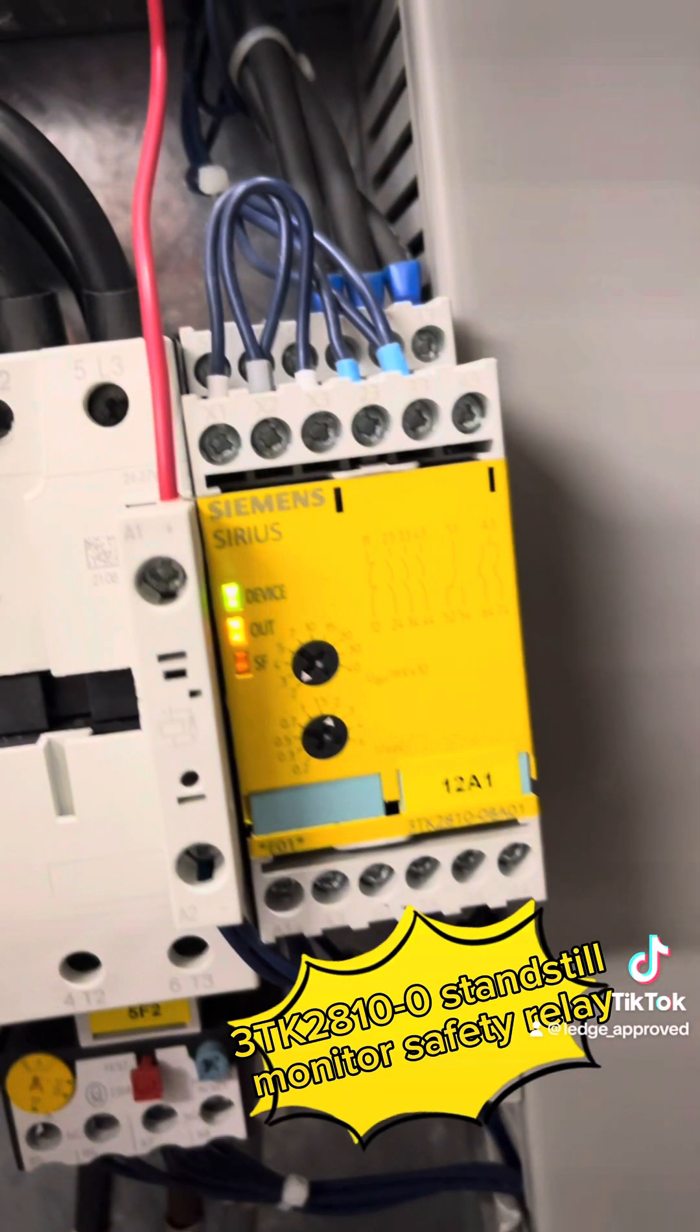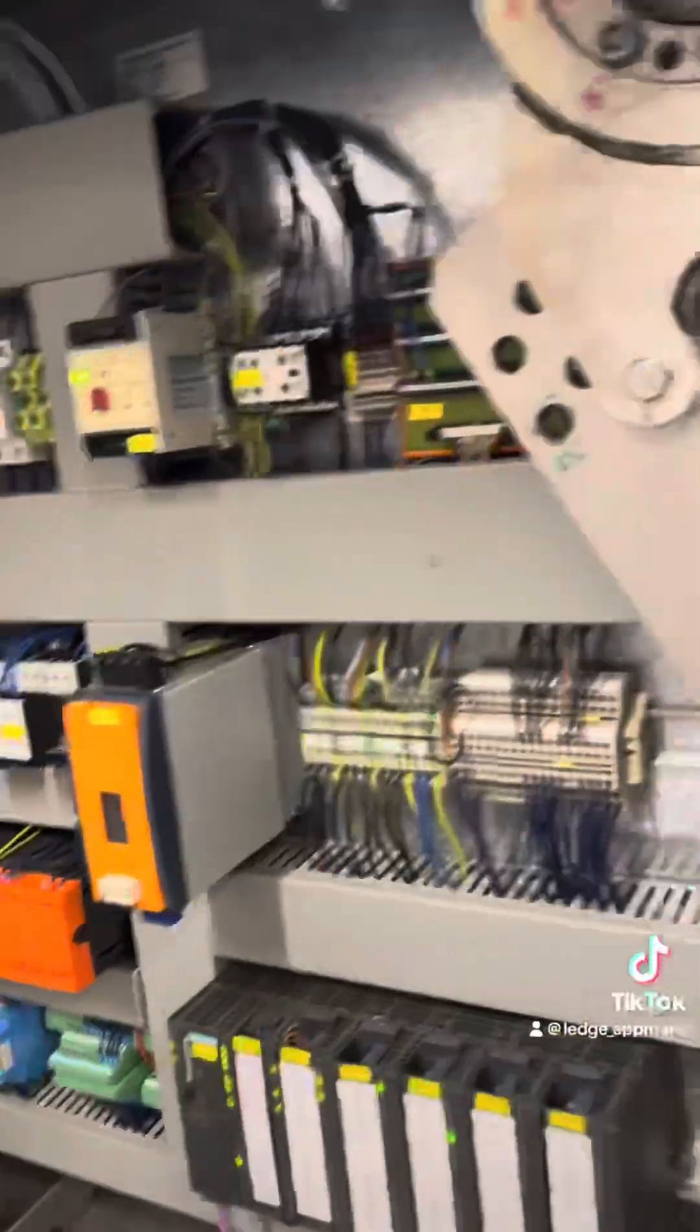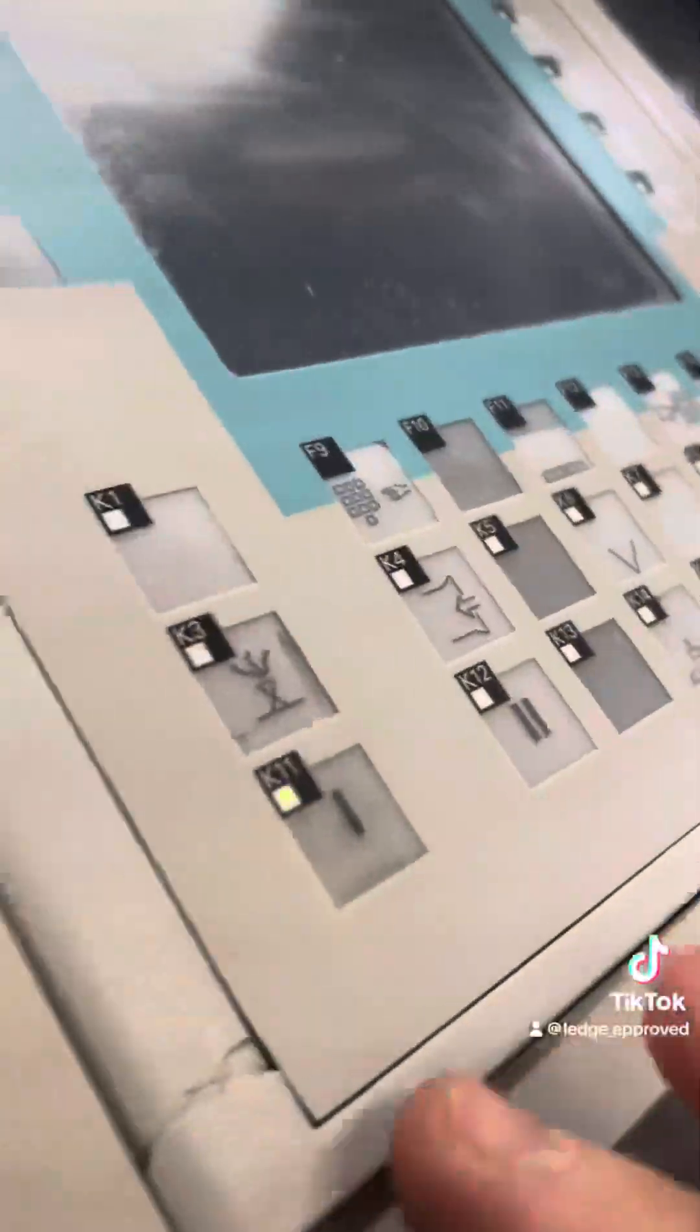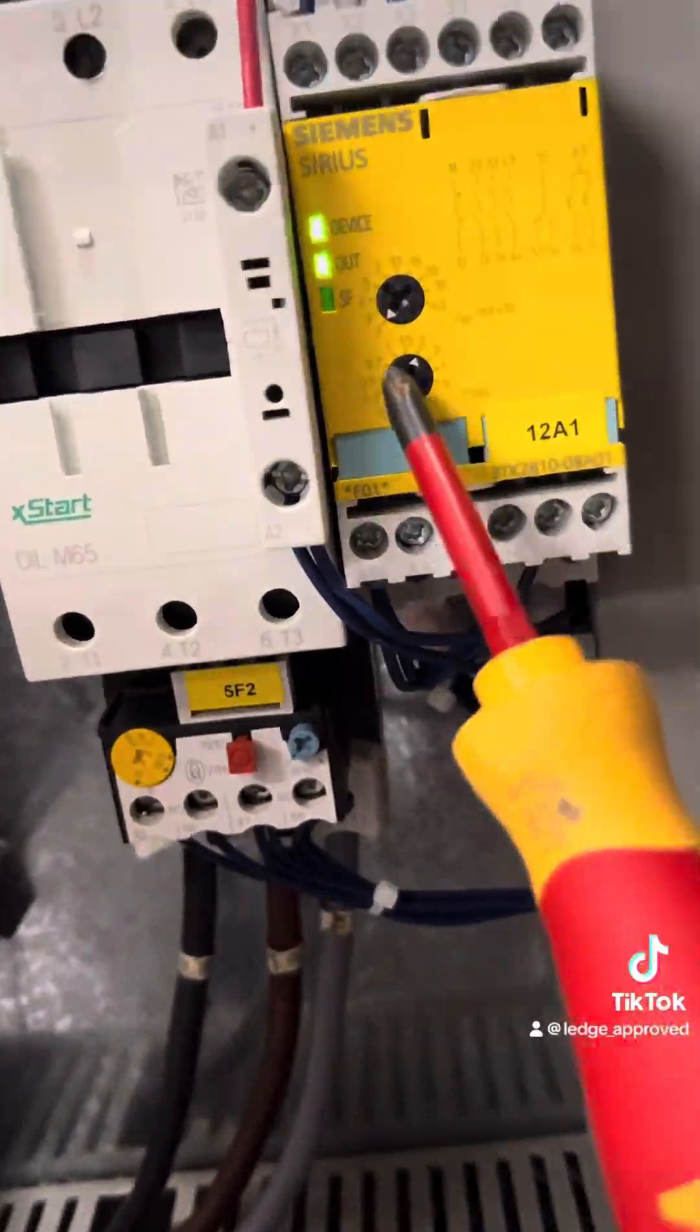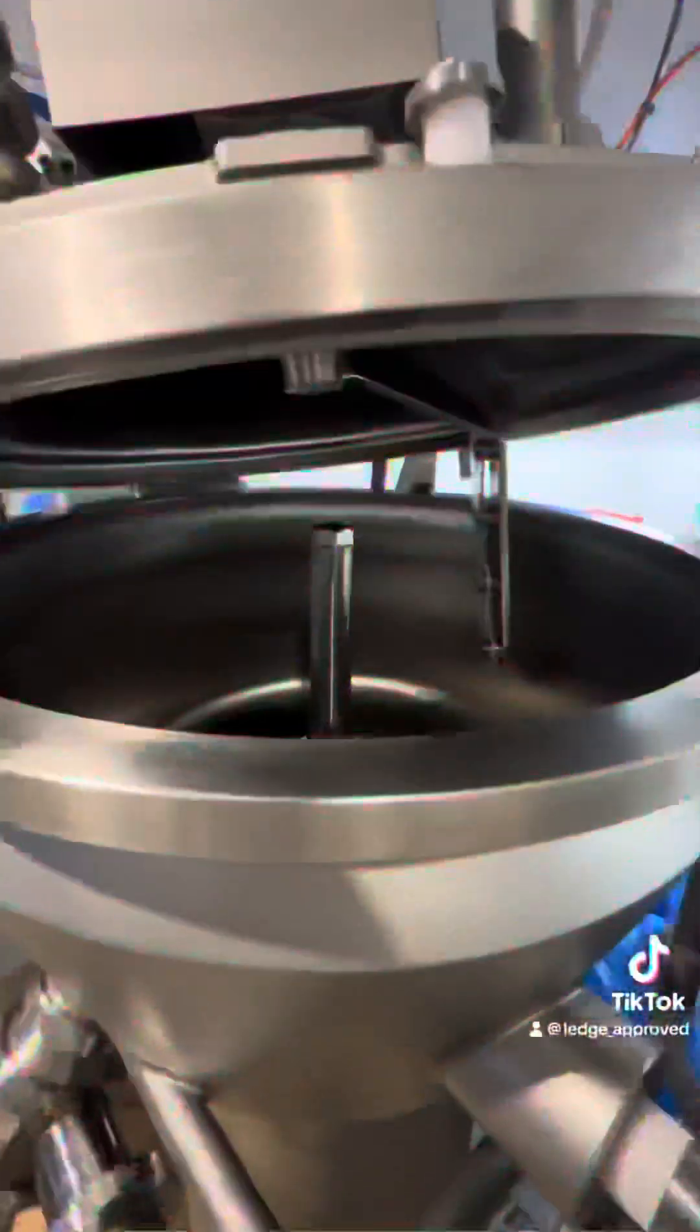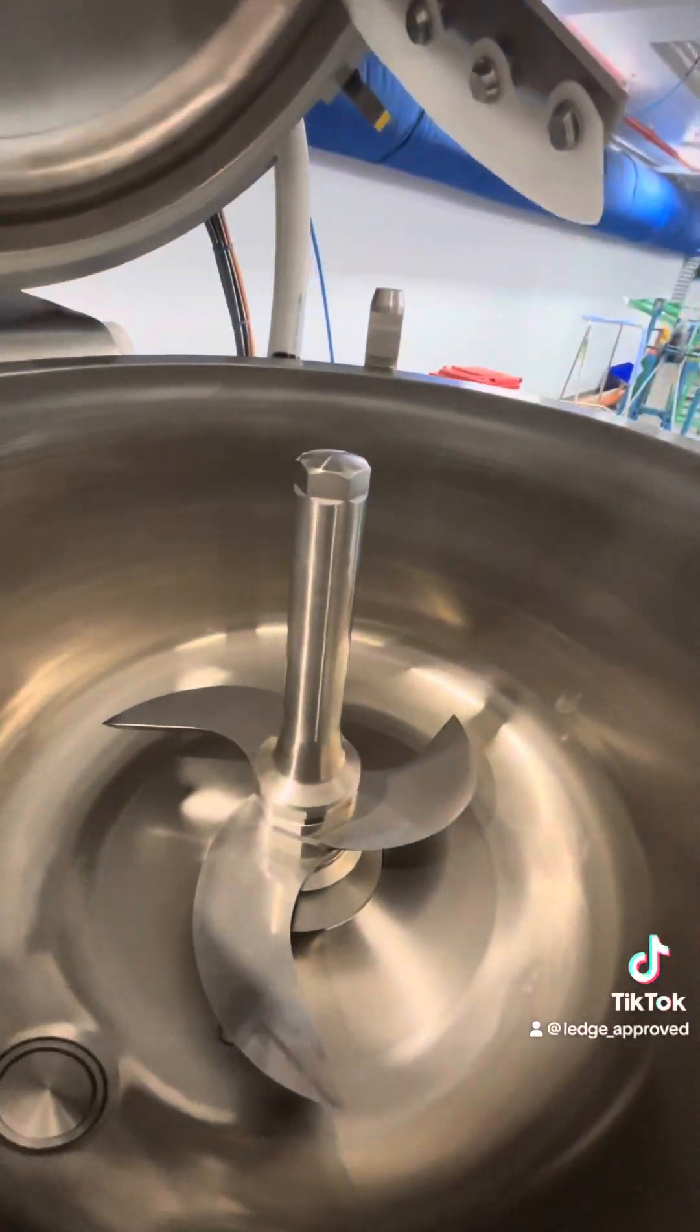What we got here is a standstill monitoring safety relay. This is monitoring a motor, making sure that you can't open the lid while it's still moving. How it's working is it's directly connected to the windings and it's checking for voltage.